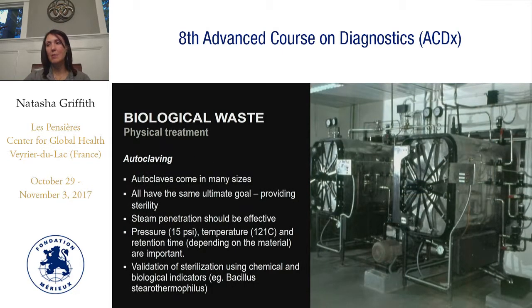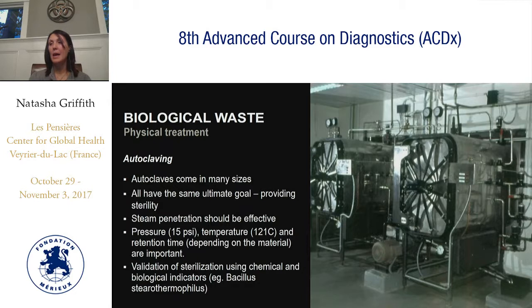Autoclaves come in many sizes. The ultimate goal is providing sterility, achieved by high steam at high temperature and certain pressure. The minimum temperature we try to achieve is 121°C, and the pressure is usually 15 PSI. When we validate the machine, we validate that it reaches the required temperature — 121°C or higher — and the required pressure inside the chamber, because that's how we can tell the machine is doing what it's supposed to do.